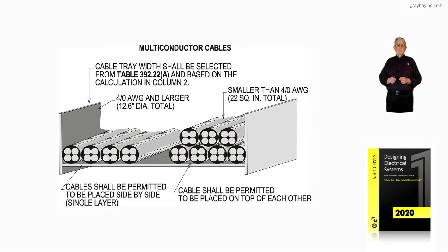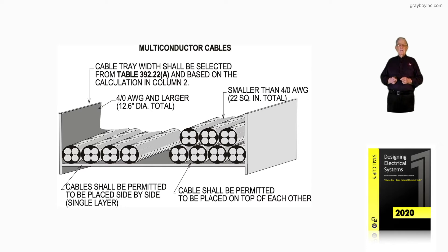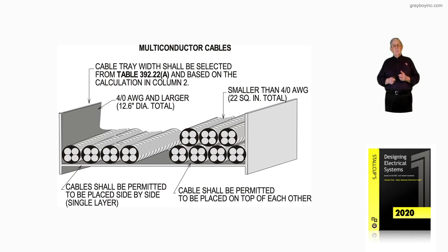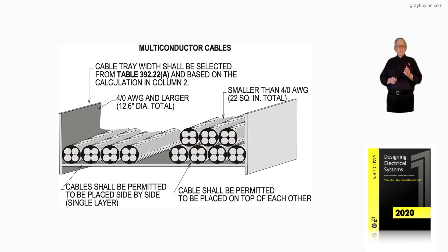This illustration deals with any mixture of cables when you're mixing them in accordance with NEC 392.22A1A through A1C. Notice in the cable tray we have multiple conductor cables, and 392.22A deals with multiple conductor cables. The cable tray width shown at the top should be selected from Table 392.22A, based on the calculation in column 2 of that table.